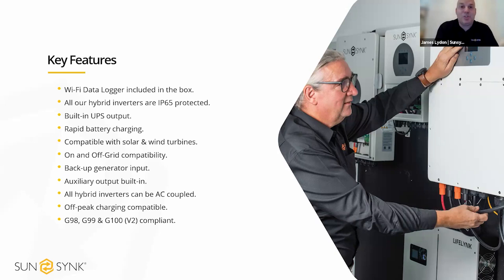For example, wind turbines produce 3-phase AC, so it's really noisy 3-phase AC that can't be used. So that 3-phase AC will need to go through a separate rectifier, and that rectifier is doing the opposite of an inverter, and that's rectifying it into DC, and that DC then comes into us.